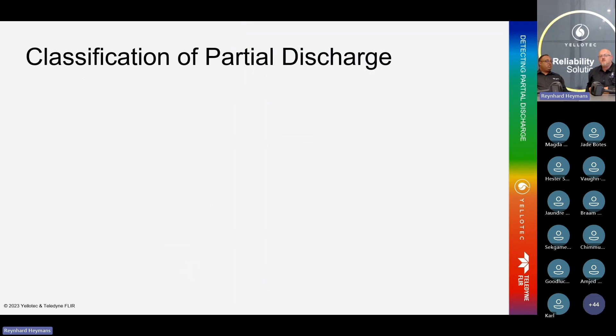And here is a good example. Partial discharge can cause things like arc flash and fire. This is an electrical treeing effect in solid dielectrics. So it's definitely a fire hazard and can cause major damage to your equipment. But partial discharge has three different classifications: one being corona, two being tracking, and three being arcing.